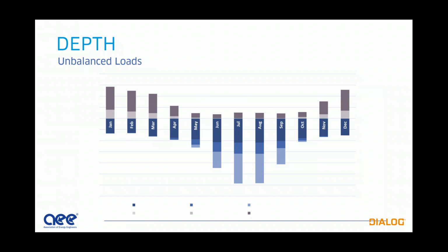Because schools tend not to have a balanced load, they are occupied through the winter and not very occupied in summer, so they're actually heating dominated. What they were finding on those old systems was that we were cooling the ground off too much by sucking too much heat out during the winter and not putting enough heat back in during the summertime. So lessons learned from those old systems, we really do need a balanced load so that you pull out as much heat as you put back into the ground. So over a long period of time, 10, 20 years, you don't end up cooling or heating up the ground too much.